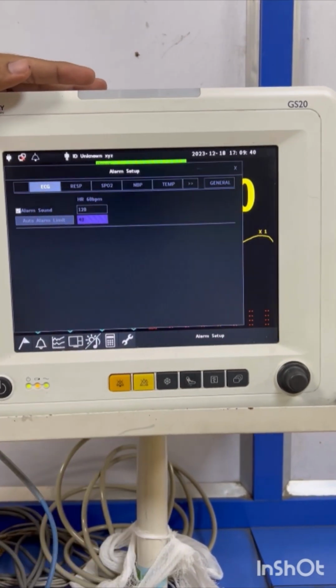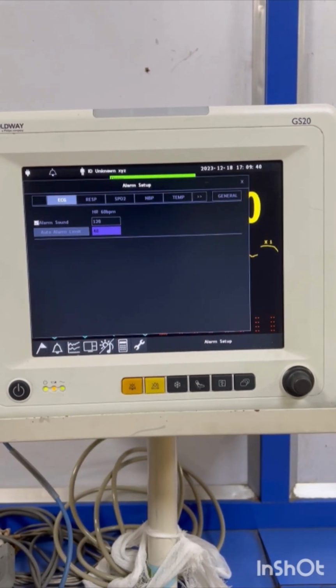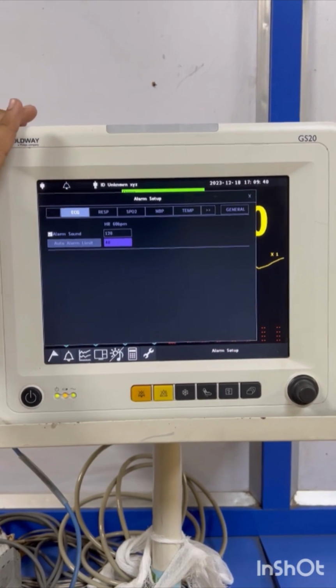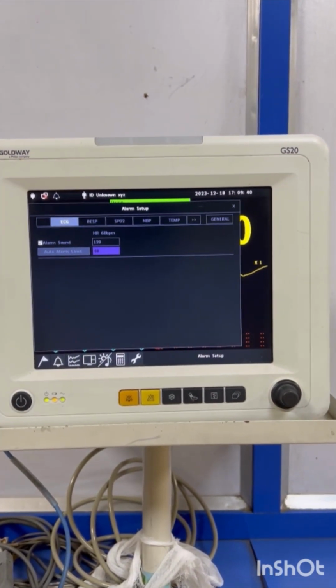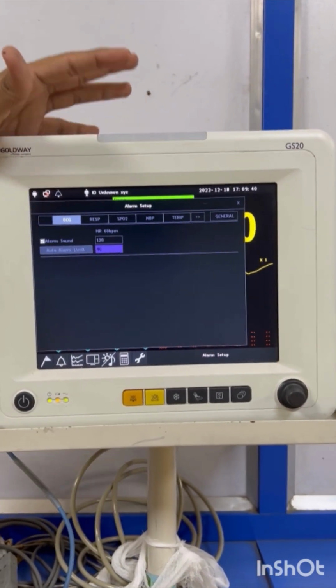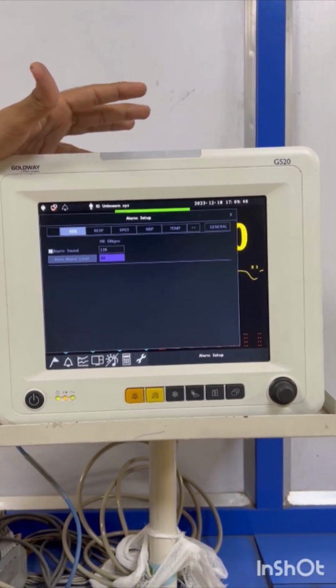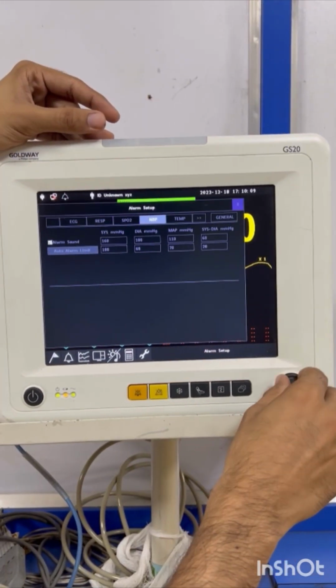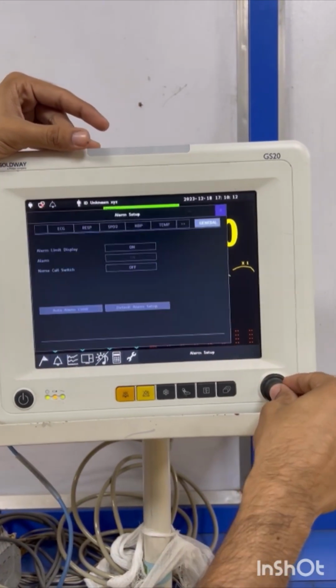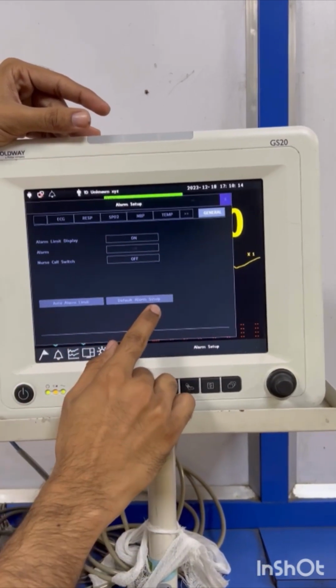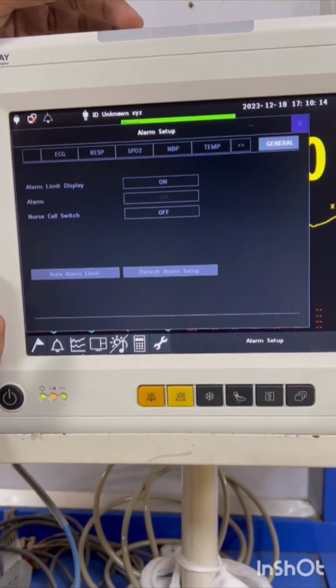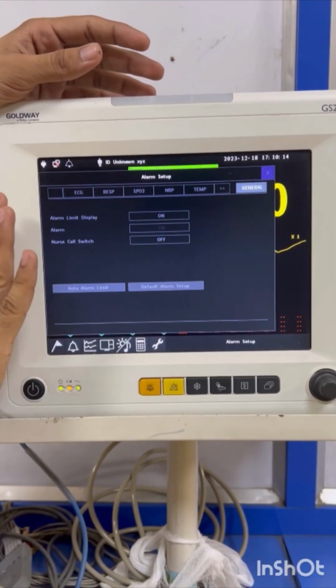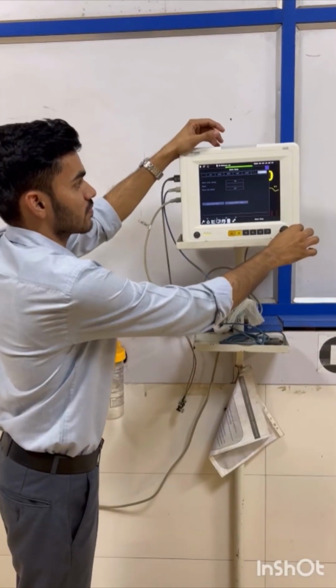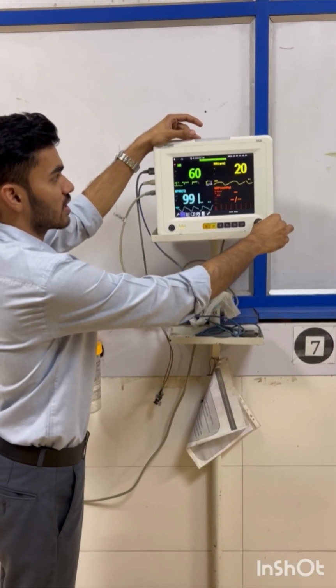All alarms are color coded. For example, if you get critical alarms, the color for critical alarm is red. For semi-critical alarm, the color coding is yellow, and for non-critical alarm, the color coding is blue. All alarms you can manually select, or you can choose default alarm setup. So monitor can automatically adjust alarm limits according to the patient type that you have selected. So make sure patient type you have selected is proper.